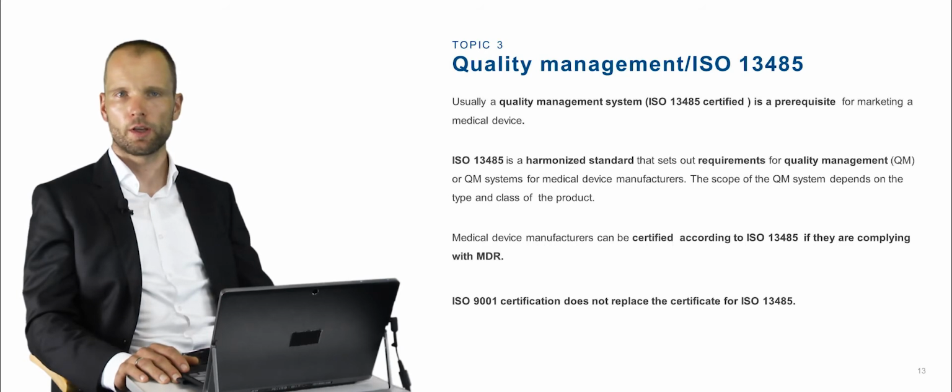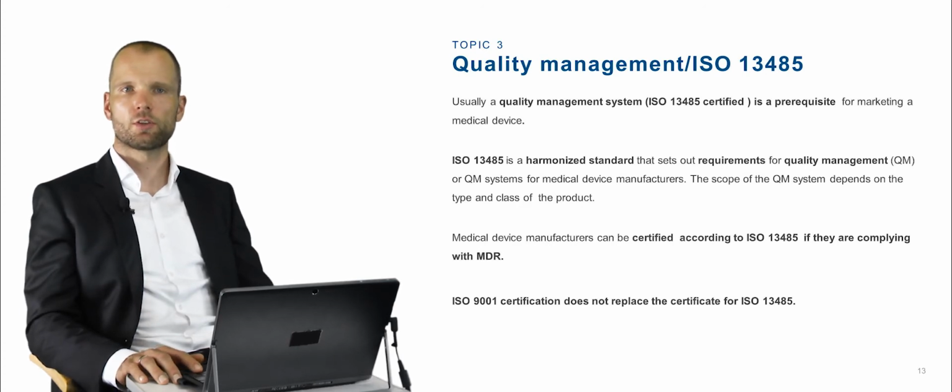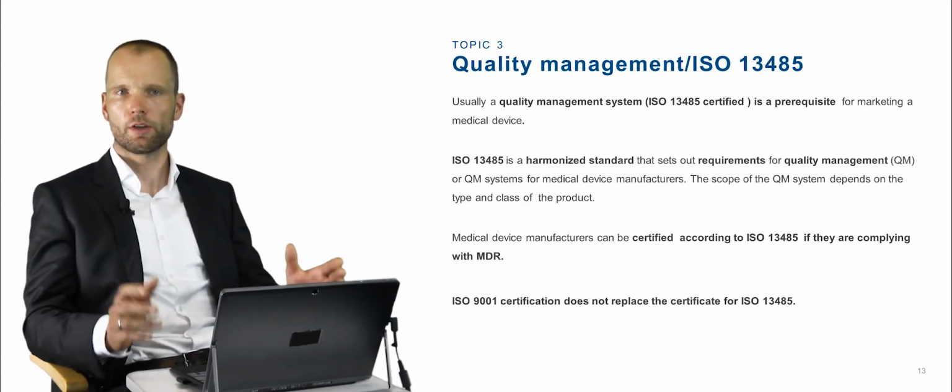The scope of the quality management system depends on the type and class of the product. Medical device manufacturers can be certified according to ISO 13485 if they are complying with medical device regulation. ISO 9001 certification does not replace the certificate for ISO 13485.